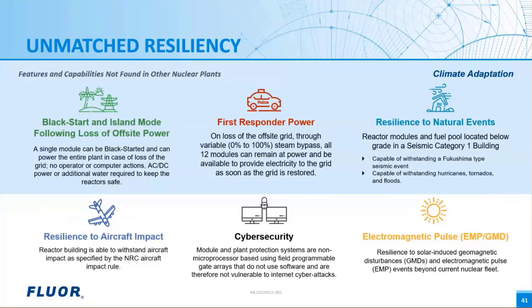Third, the NuScale small modular reactor is more resilient to natural events. With the reactor located below grade in a seismic category 1 rated building submerged in the ultimate heat sink, it's protected against lots of natural disasters. And like all other nuclear plants, it's designed to withstand high winds from tornadoes and hurricanes up to 190 miles per hour and large earthquake motion rated at 0.5 G's of peak ground acceleration for the NuScale SMR. So it's very resilient to natural events. And as we've seen time and time again in the USA, the nuclear power plants are the ones that survive large natural disasters, and the NuScale plant will survive as well or better than these previous reactors.